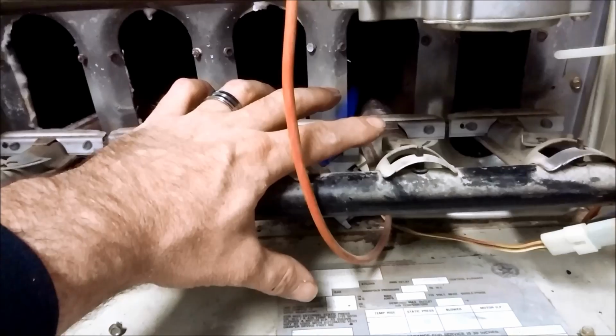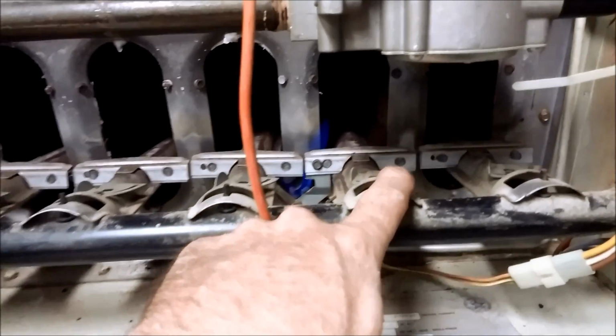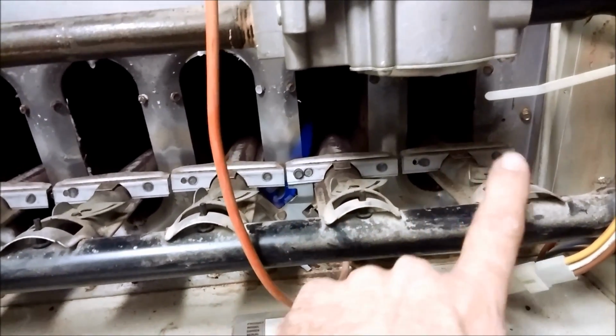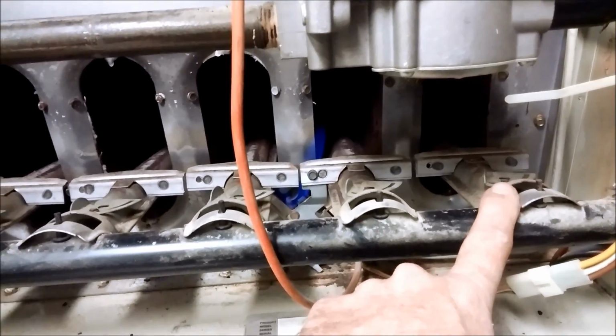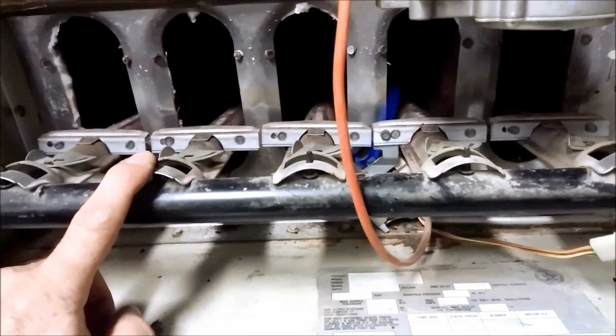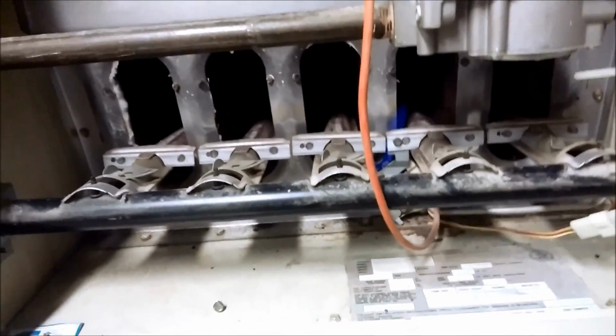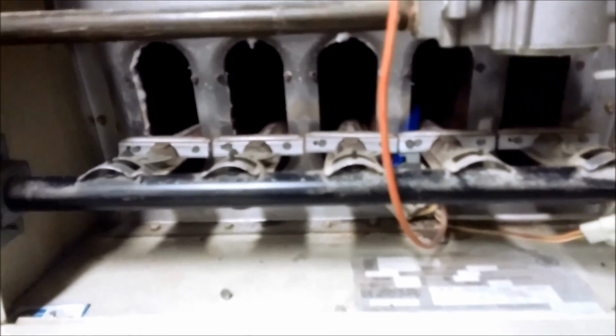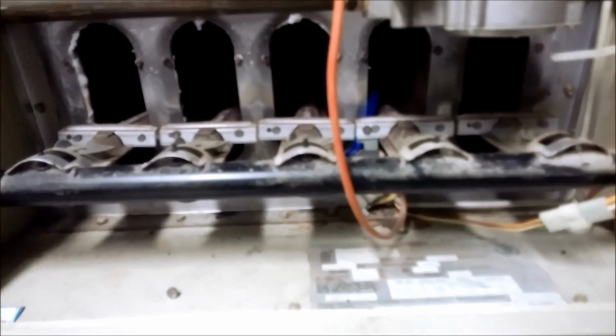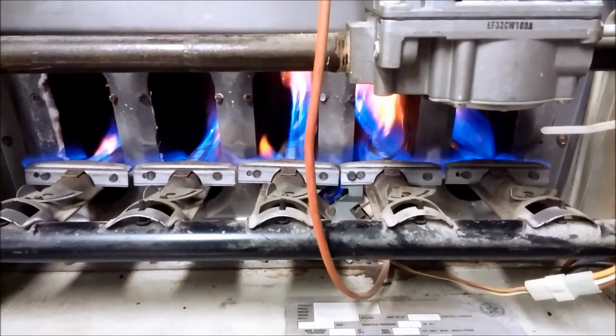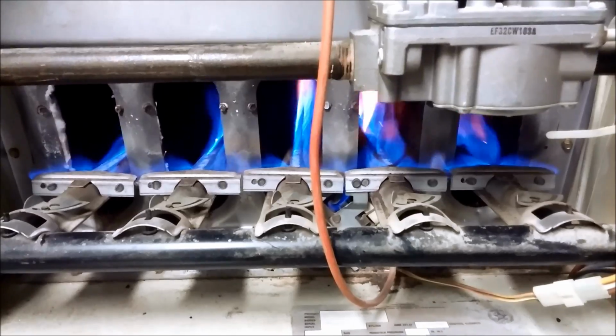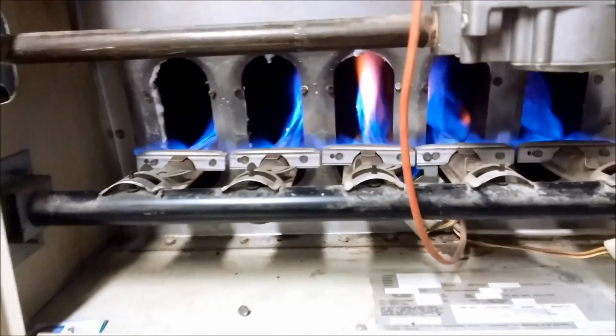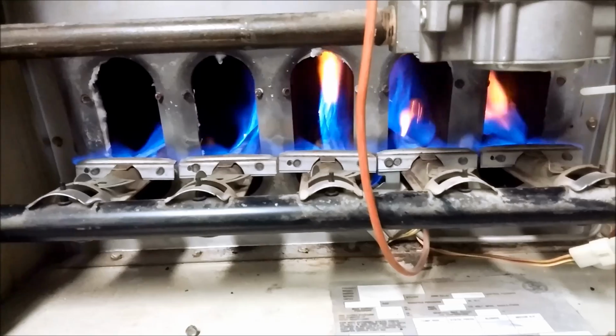And this cell, this cell, this cell, and this cell are cracked. Well, no, this cell and this cell are cracked wide open. This one has a smaller crack in it. This one has no crack in it. Needs a 3-wire pilot. It should have lit by now, but give it a second. Okay, we're lit.